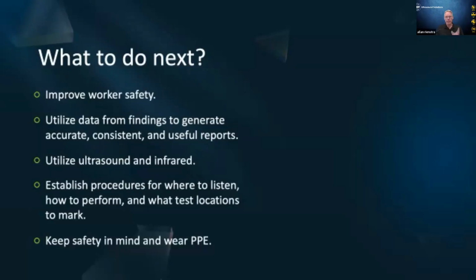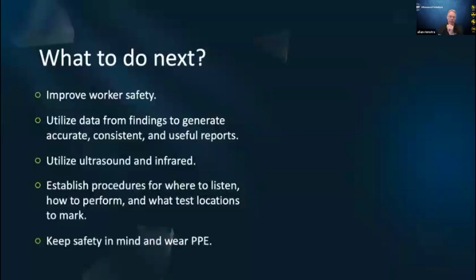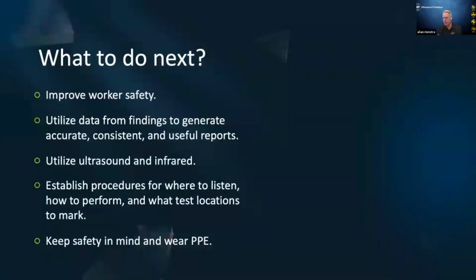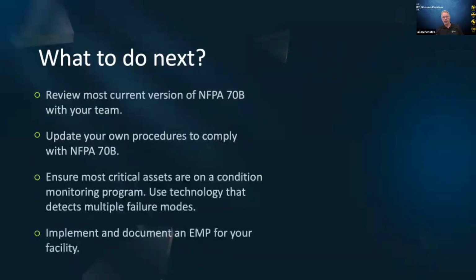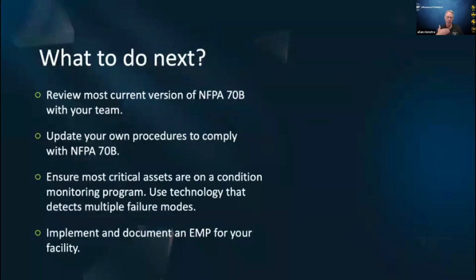Establish clear procedures. Define exactly where to listen and how to perform inspections and which test locations should be marked. Consistency is going to build reliability. And obviously, always wear your PPE. Never compromise on safety. Proper personal protective equipment is not negotiable. If you haven't already done it, purchase the standard, review the most current standard, the 2023 standard. Make sure your team is working from the latest edition. The 2023 update turned guidance into enforceable standards. Update your internal procedures. Bring your own procedures into alignment with NFPA 70B so your practices are matching industry expectations.